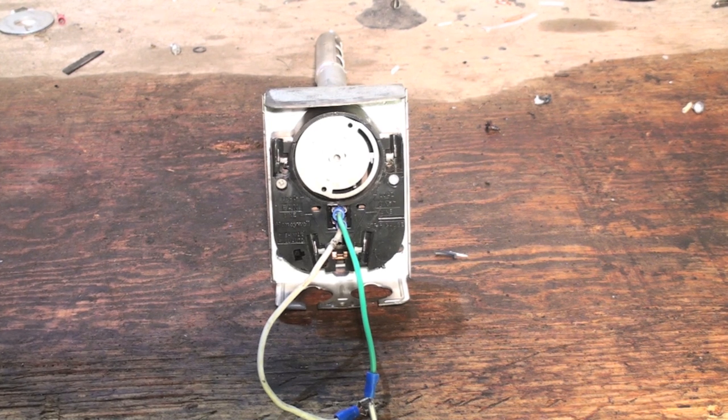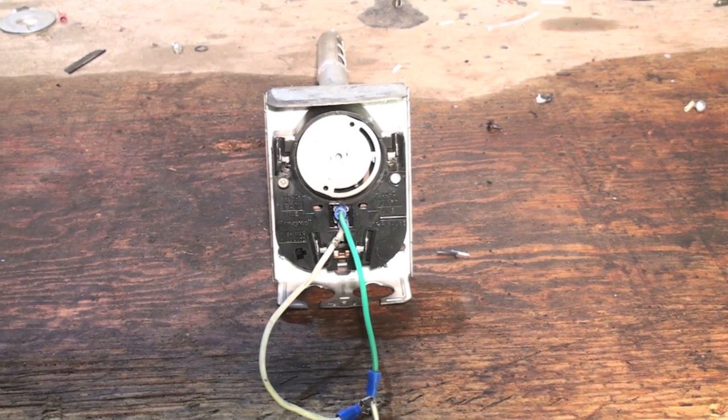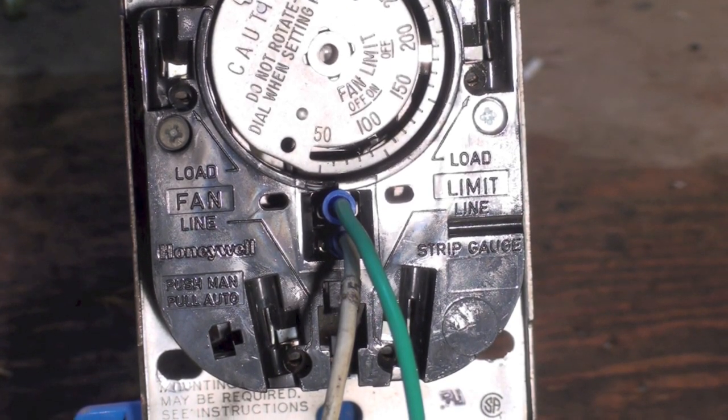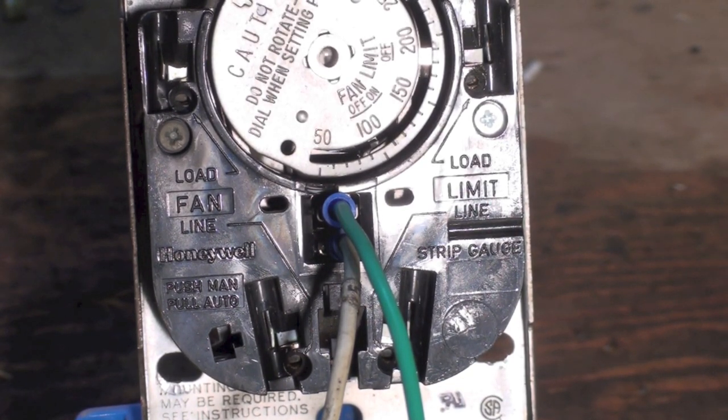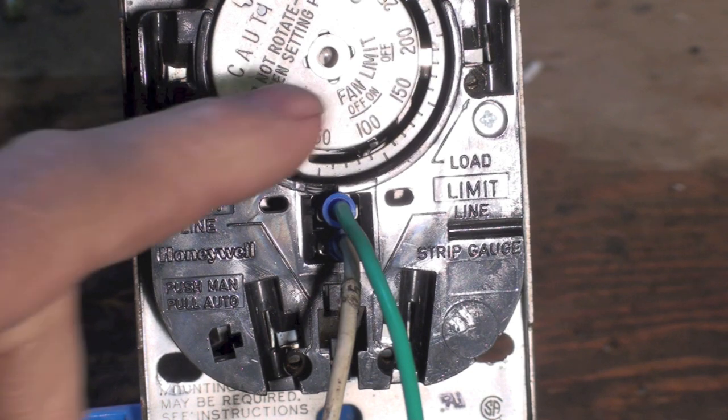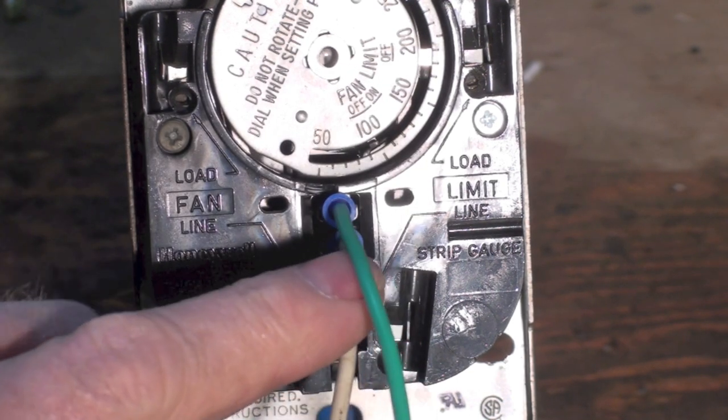Okay, a little closer here. This is a normal Honeywell fan and limit switch with the limit switch on one side and the fan switch on the other, and a spiral bimetal that moves the switches. But this one has two wires coming right here. Now I'm going to pull those wires off so you can see where they actually hook up.